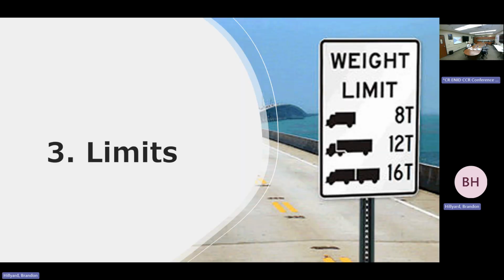So then limits. All MVs and CVs have limits. They're generally high or low limits, but they could even be a target. Another thing to think about, real quick, is that feed forwards don't have limits in APC, obviously, because they can't be controlled by APC. So the other independent variables do, and the dependent variables.